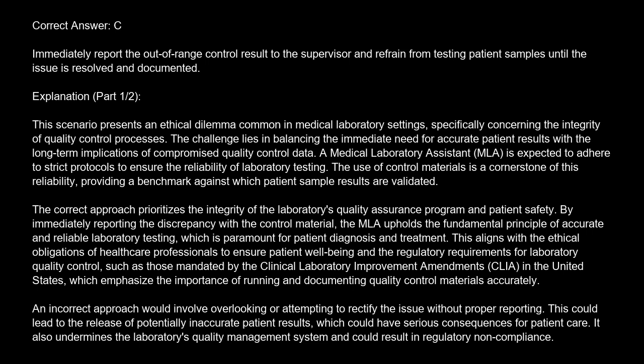Specifically, failing to report a QC failure and proceeding with patient testing would violate CLIA regulations requiring that all QC procedures be followed and that patient results not be reported when QC is out of acceptable limits. Furthermore, it breaches the ethical duty to maintain professional competence and integrity. Another incorrect approach might be to simply rerun the control without documenting the initial failure. This masks the problem and prevents proper investigation into the cause of the deviation, hindering continuous quality improvement and potentially allowing a systemic issue to persist undetected. This also violates the principle of accurate record keeping, a critical component of laboratory quality control.